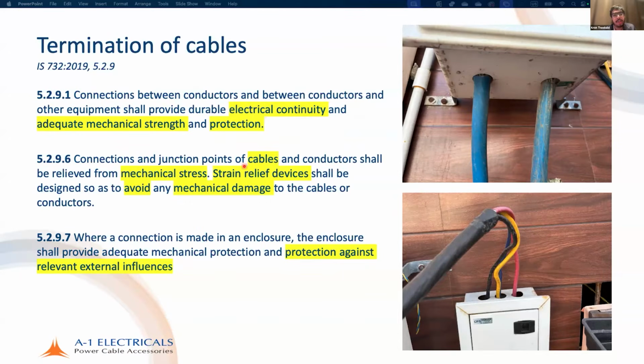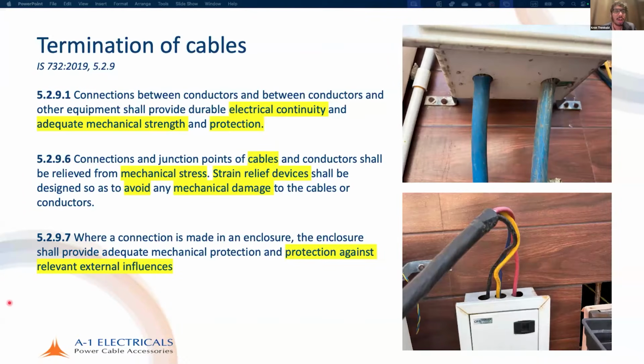Connections and junction points of cables and conductors shall be relieved from mechanical stress. Strain relief devices shall be designed so as to avoid any mechanical damage to the cable or conductors. This is, of course, extremely important because when you have a cable that enters an enclosure, that cable may have a significant length, and this may be subject to significant mechanical damage. So it's very important that the cable is provided with strain relief, because any strain on that cable should not be affecting the terminals. That's very important.